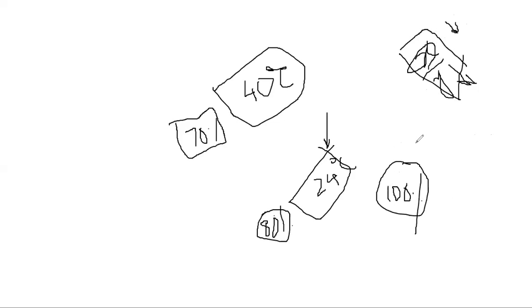What does it mean? Some mass of water has come out from the air, and after that, if we increase, that is called dehumidification, because some water is removed from the air. And after that we reheat to bring back, because when you do the dehumidification, it will reach 100% relative humidity at this temperature. After that you reheat, and then you bring it back to the correct humidity level.